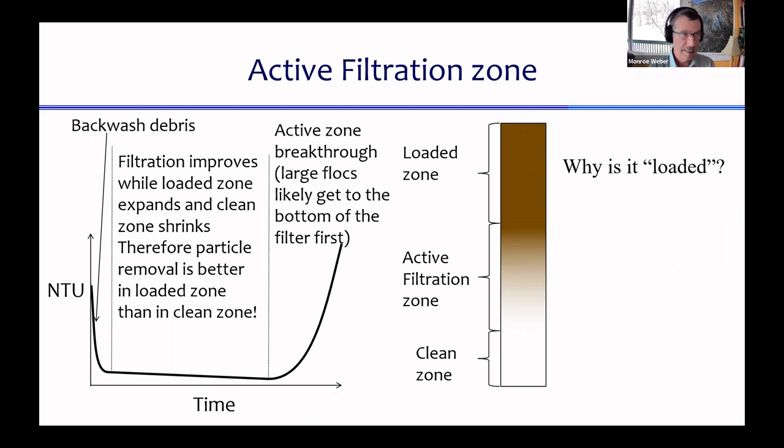And this is commonly seen in filters, and it suggests that the removal in the brown zone, where the filter is supposedly full, that particle removal there is actually better than in the clean zone that's at the bottom of the filter.